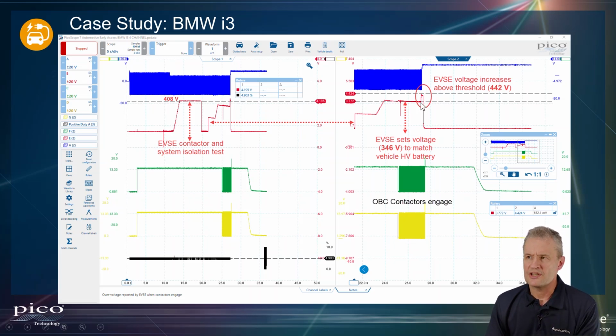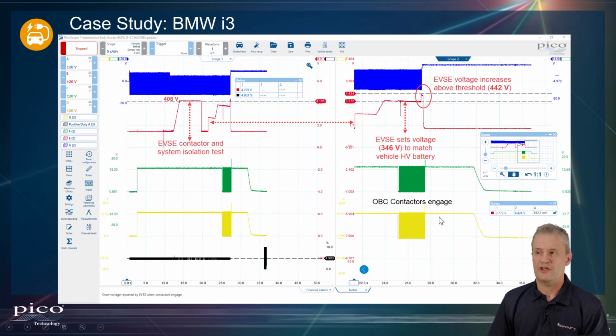At this point, you'll notice as the voltage has crept up at the charge inlet, CP communication has halted, so charging will have stopped, safety-wise. The onboard charger contactors have also opened. You see here on the right-hand side, channels C and D, they were controlled with PWM, and they've now opened. This is the error, the initial error message, no further charging. So the message here really is that the voltage at the charge inlet was creeping up far higher than the onboard battery. Where to next?